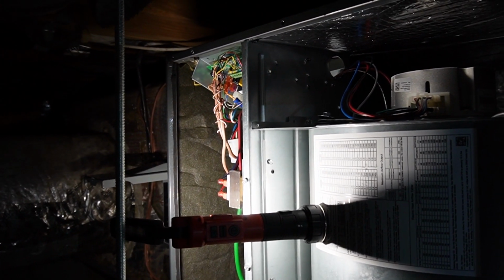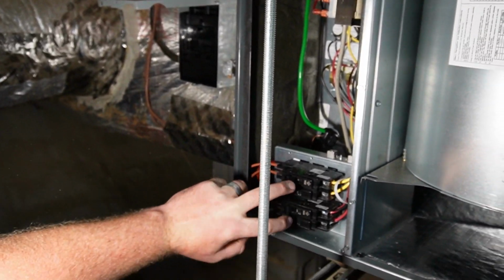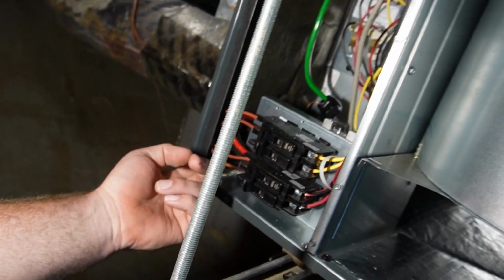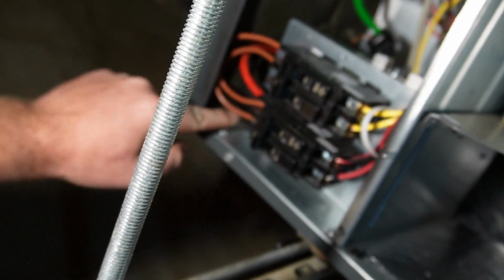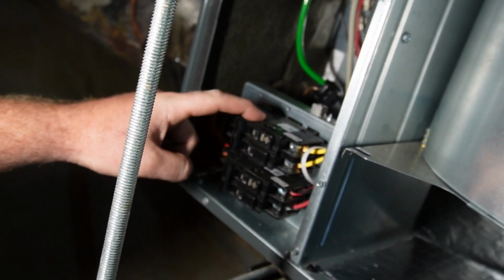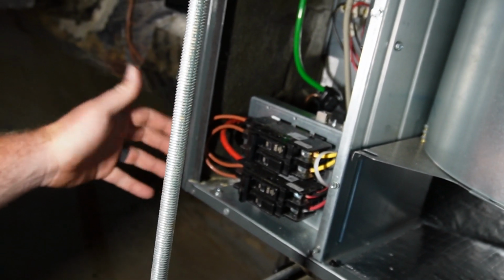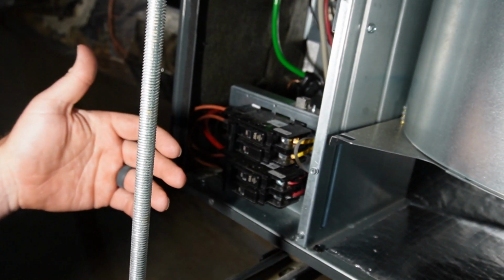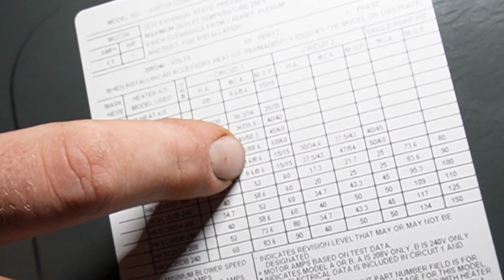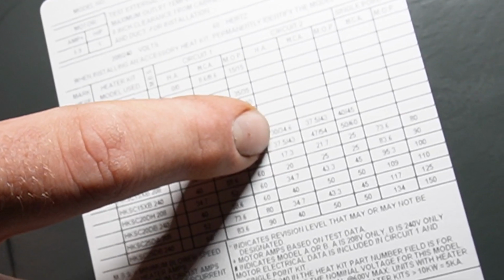So internally there's a 50 amp breaker. As you can see, you've got your standard disconnect that runs to a dual point setup, and they have a double lug going into the second breaker. So a 50 amp setup for 15 kW of heat plus the furnace. Over here, that would be a 15 amp breaker and a 45 amp breaker, the HKS15.